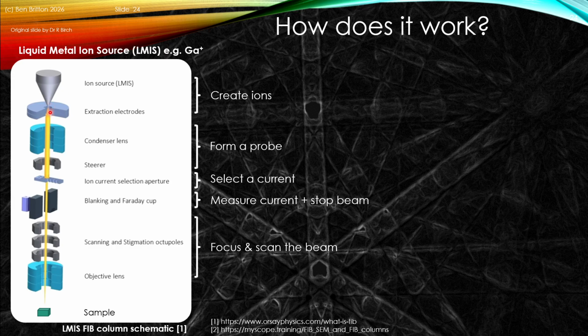down the primary column. And then we can have a condenser lens to shape the probe. We can steer this across a particular ion current selection aperture set. And then we can have measurement of the probe current as well as blanking of the beam in a beam blanker and Faraday cup system. And then we can have the scanning and stigmation to improve the shape and where the target beam hits our sample.